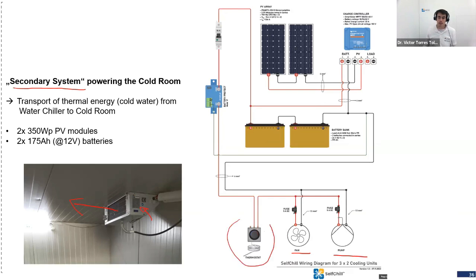But this thermostat is not in the water chiller. This thermostat is inside the cold room, right? Why? Because this thermostat stops the fan and the pump once the set point temperature has been achieved. So if, for example, you want 10 degrees in the room, you are getting cold air at 5 degrees. Once the cold room temperature is below 10 degrees, the thermostat will stop the circuit, and the fan and the water pump will stop. This is how we control the system. On one side, we control the cooling units. On the other side, we control the water pump and the fan, the heat exchanger. If there is any question regarding how the system works, or regarding the wiring diagrams, please let us know.